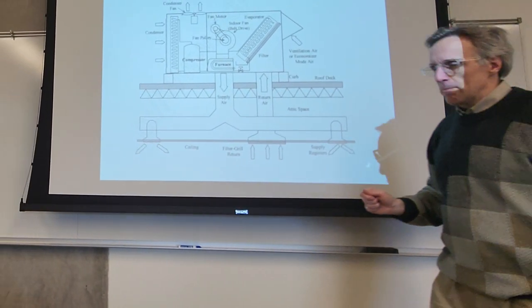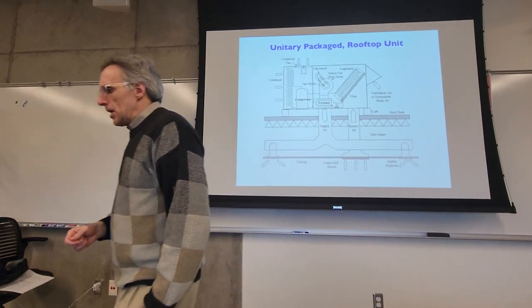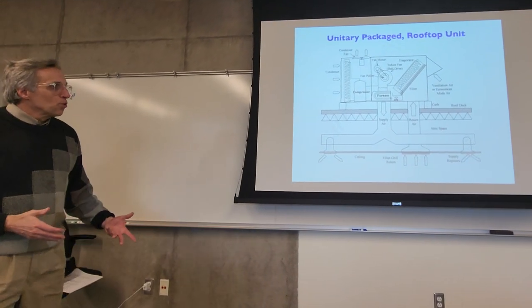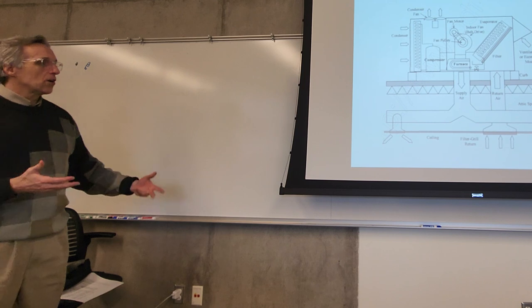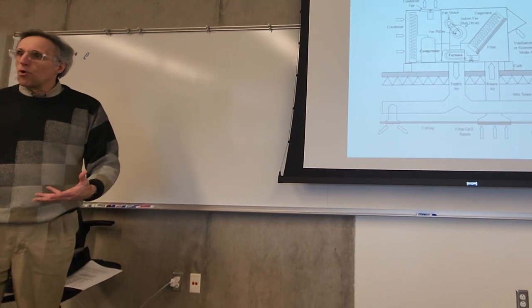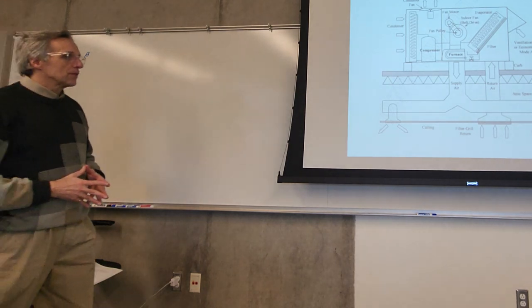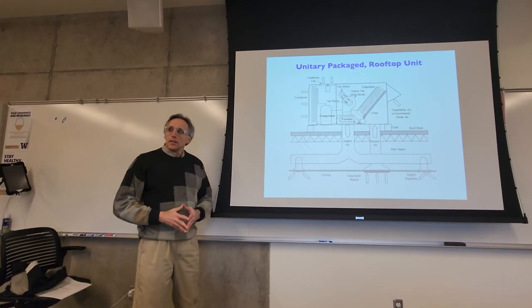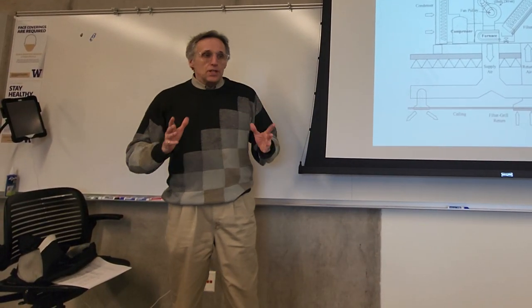These have problems controlling humidity. They often overcool. You get too much cooling, that causes the humidity to go up, and you can get mold and things like that. So they're not great in really hot, humid environments, or when you need to have really good humidity control.